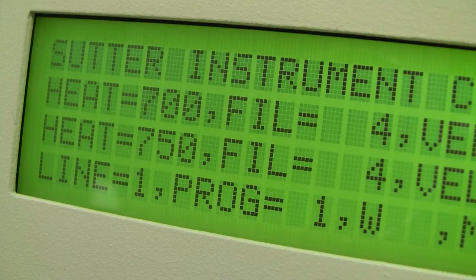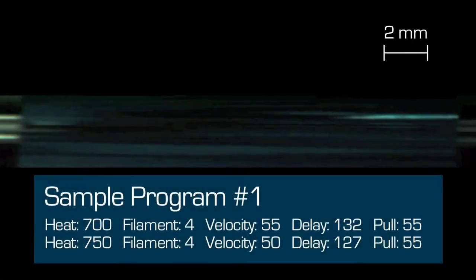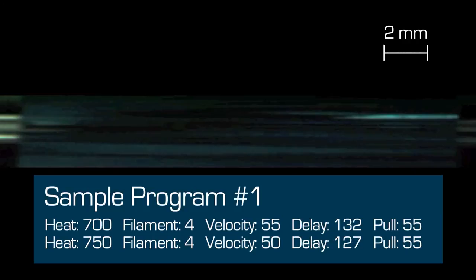Your puller comes pre-programmed with a two-line sample program in position 1, which can be used as a good starting point for pulling patch pipettes from 1mm quartz glass. Should the sample program have been overwritten, you can copy the parameters from the subtitle here.